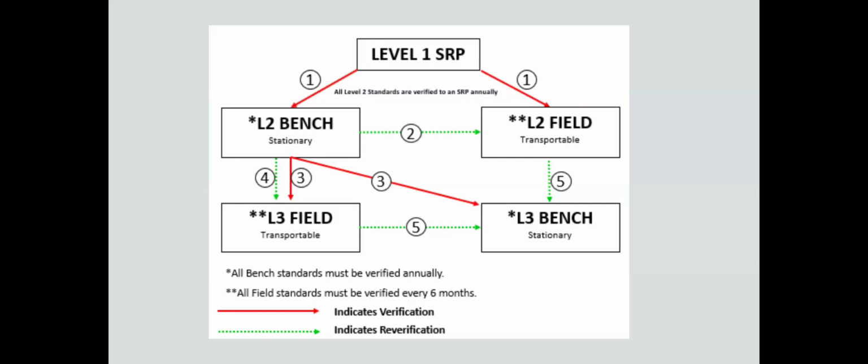Thanks, Leroy. Yes, what you mentioned there is pretty important. What we do here is we have that one level 2 bench for the maintenance and cal group, and we've got 6 level 2 fields. Before and after they go to EPA, we do a re-verification to make sure that, 1, it's fit to go to EPA, and 2, it comes back in one piece, because a lot of times we have to ship to various regions that can accommodate us on our schedule. With Region 8, usually we can drive down, but if we have to ship to Region 7, because Region 8 can't accommodate us, or we have to ship to RTP, we definitely check it when it gets back.